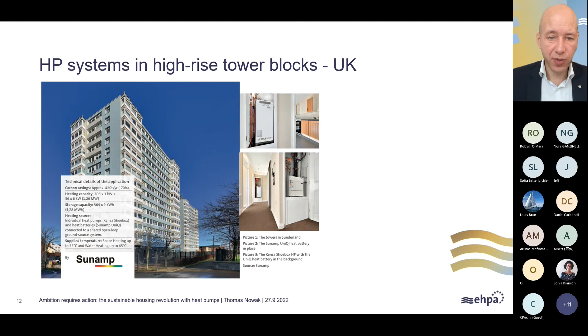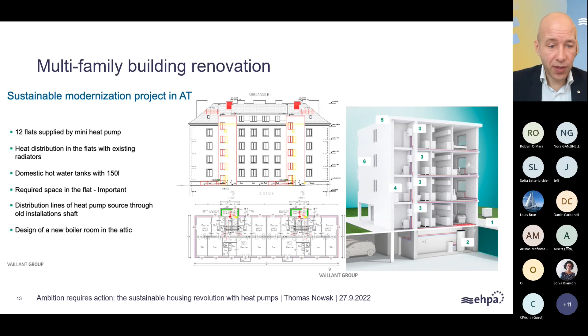You have a central heat source and several mini heat pumps, some people call them booster heat pumps, but the important thing is that you put them at the apartment level. Depending on design, you can even put cooling services into the apartment. You connect them to a hot water tank, so everything needed in the apartment is provided at the apartment level, and then there's a loop through the building, which you could call district heating, if you could call the building a district, providing heating and cooling at the same time.